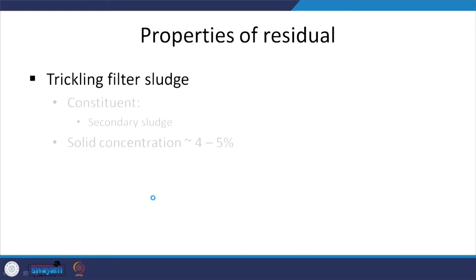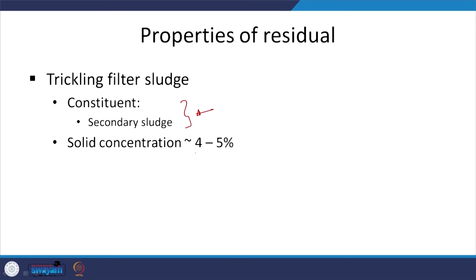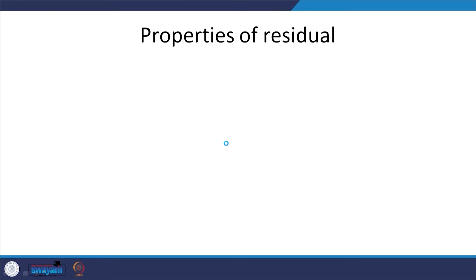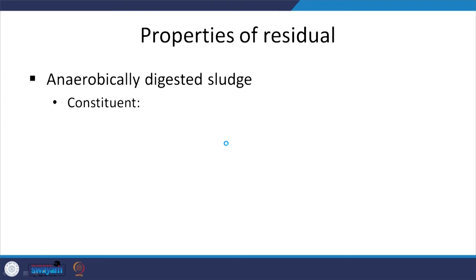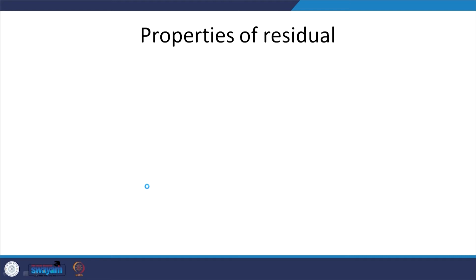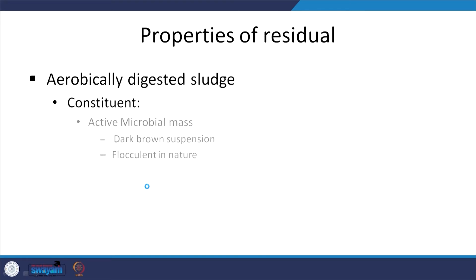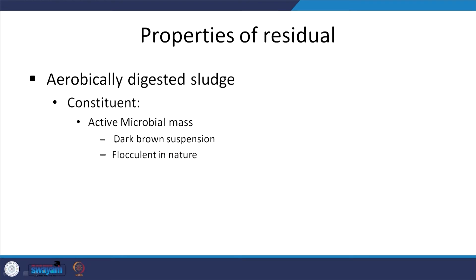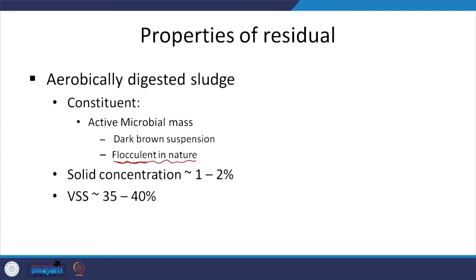Trickling filter sludge — which we did not look at — is similar to that of the secondary sludge, with solids concentration relatively higher and suspended solids in a similar range. Anaerobically digested sludge — what we have after digestion by anaerobic process — we still have a microbial mass but it is going to be relatively inert. Solids concentration is increasing and suspended solids percentage is decreasing. For aerobically digested sludge, the relevant mass or microbes are flocculent in nature, making dealing with that later difficult. Solids concentration is 1 to 2 percent and suspended solids relatively lower.